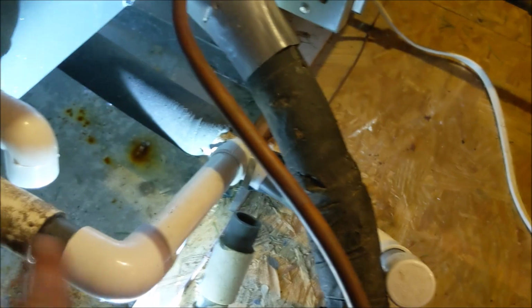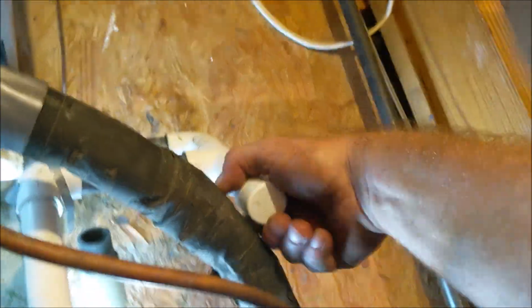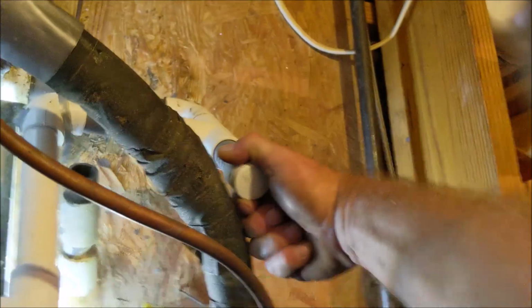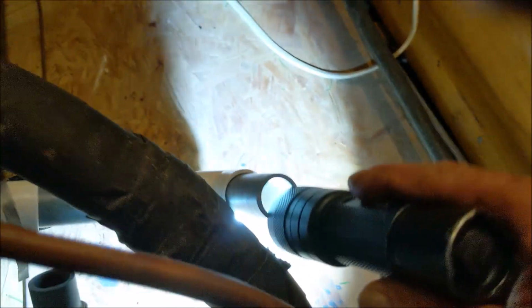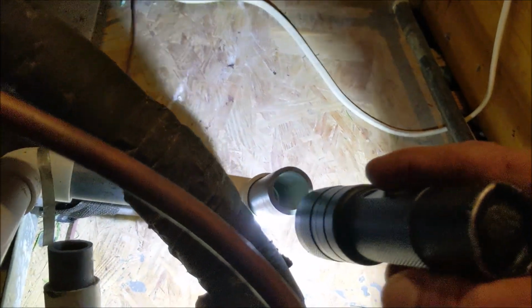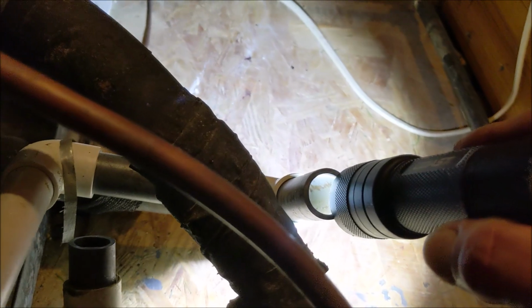They only insulated here. None of this is insulated. We always do recommend insulating the entire pipe. Let's see if we can get this cap off. And let's see if we can shine the light down in there. Oh yeah, it's clogged. So this line probably needs to be blown out really good, because you can see that water just rising up in there.